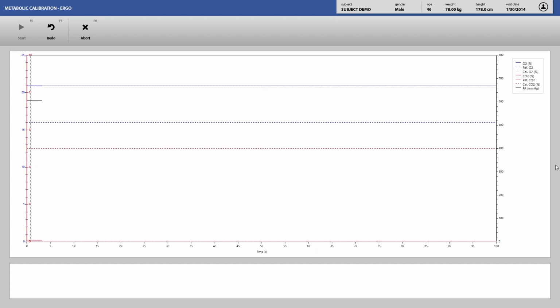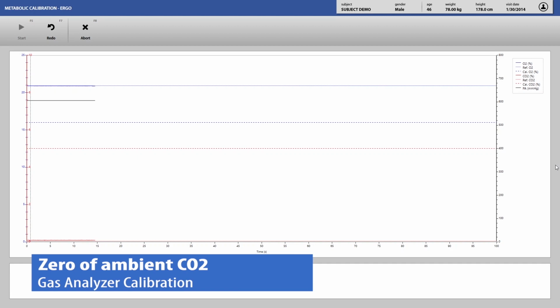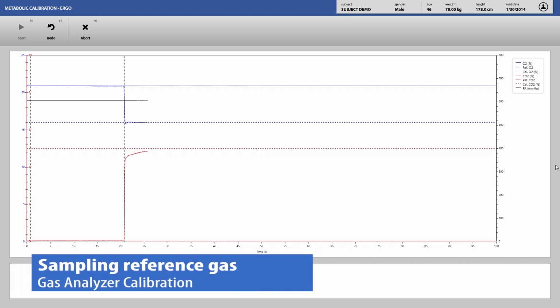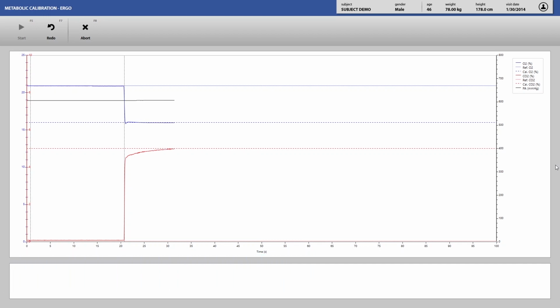Gas analyzer calibration needs to be done immediately before every test, after the exchange of the gas cylinder, after the exchange of the gas sample tubes, and when measured results are doubtful. It is essential to make sure other spare parts, consumables, and fixations are working properly. Pressure of the calibration gas cylinder needs to be monitored. Expiry date of the calibration gas needs to be checked.